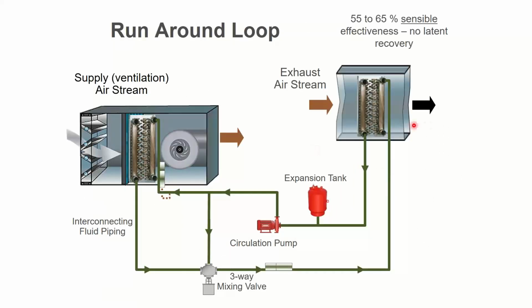Runaround ERVs, like I said, are not going to meet code because they only do sensible. So if you have to have an ERV for code compliance, this doesn't help you. But if you have a big building and you want to just do it, if you have exhaust on one side of the building and fresh air on the other side of the building, a long distance between them, that's when this would make sense. You drop a hydronic coil in the exhaust, a hydronic coil in the fresh air intake, and you put a circulating pump between them to move the BTUs from one to the other.